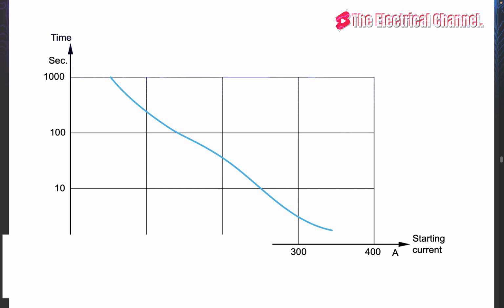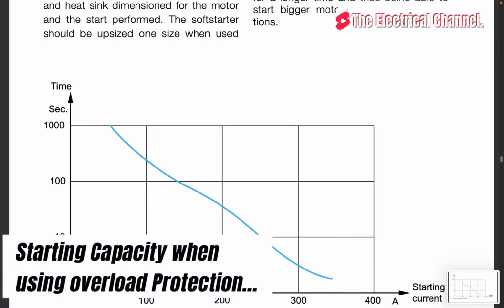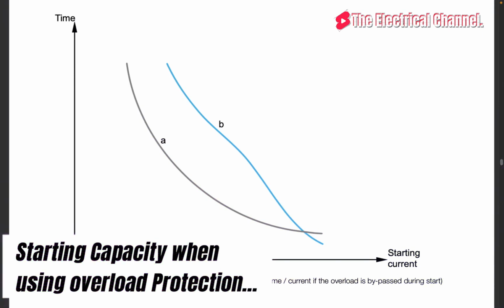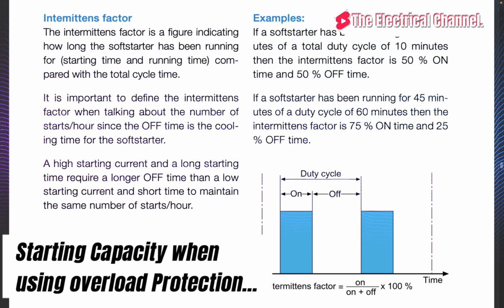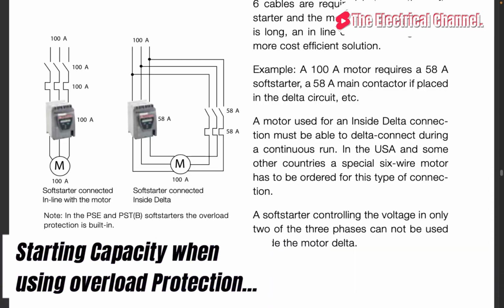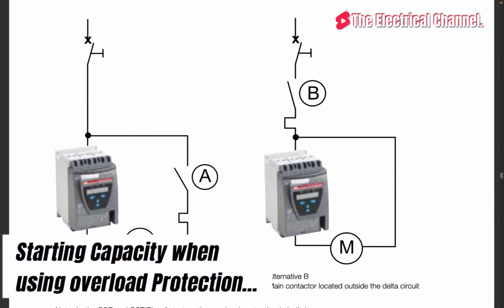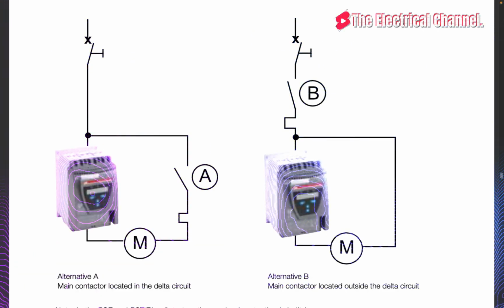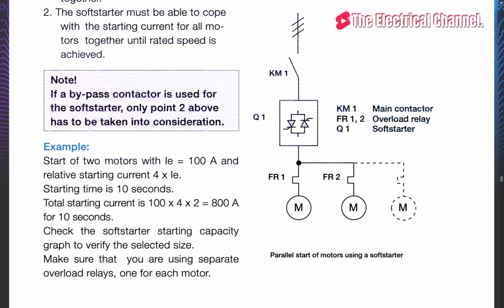The overload protection for the motor, thermal or electronic, will very often set the limit of the starting capacity. These overload protections have different tripping classes, describing how fast they are tripping for a specific current. A Class 10 relay is used for normal start in general, while a Class 30 is used for heavy-duty starts, where the start usually is longer.